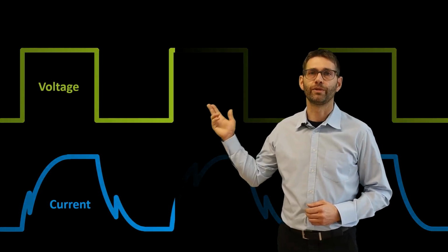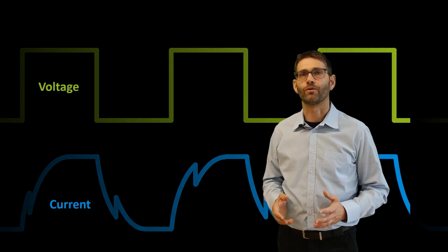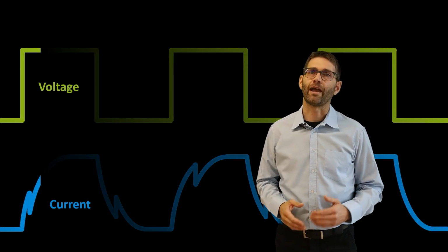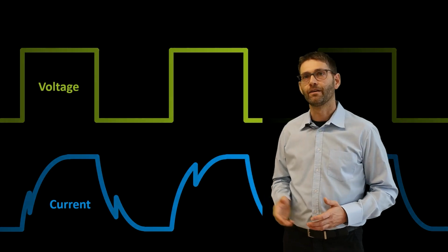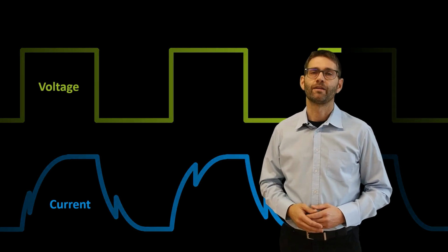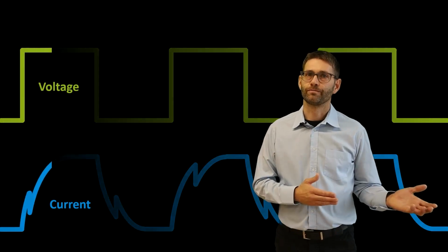and voltage, green curve. The course of the curves allows conclusions to be drawn about the operating state of the brake and the wear. If, for example, the two peaks in the blue curve are missing, the brake has not switched, despite the current being applied, and an error signal is output.